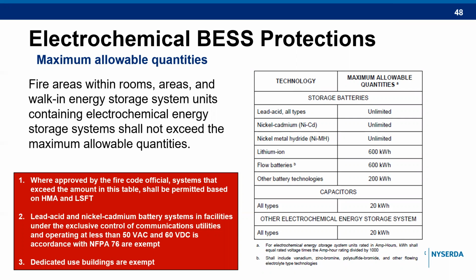But you can go beyond that if the large scale fire testing shows that it is safe to have a system larger than that. So that's where that first number 1 in the red box here says, where approved by the code official, systems that exceed the amount in the table can be permitted based on the hazard mitigation analysis and the large scale fire testing that we talked about before. So anytime you want more than 600 kilowatt hours of lithium ion batteries, it's going to trigger that hazard mitigation analysis and that large scale fire testing.